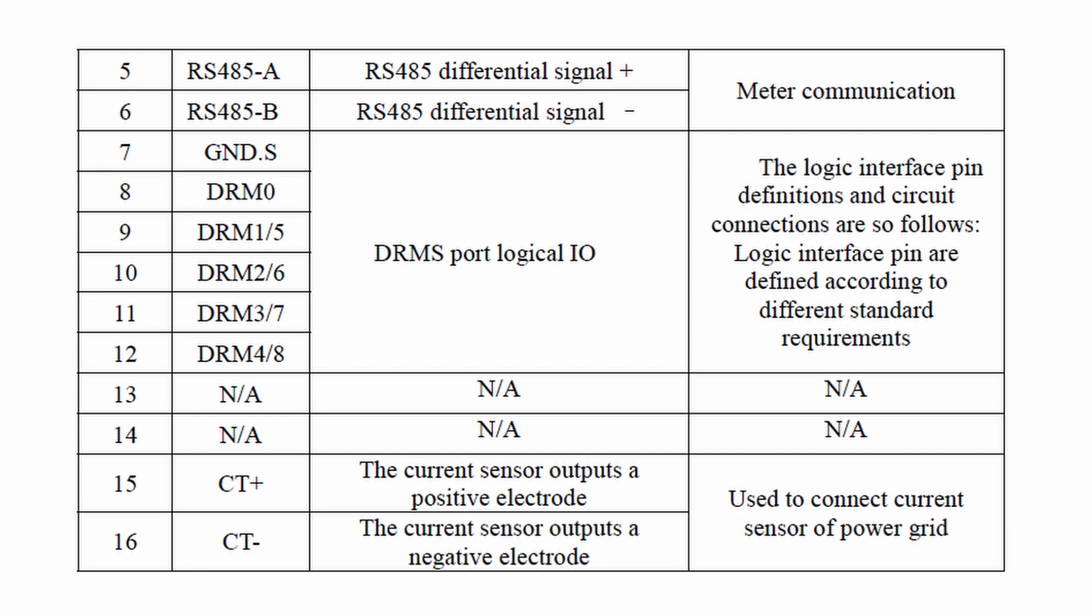The ratio on it is 2000 to 1. There's a dedicated meter and dedicated CT for that solution, which can be extended up to 1000 meters. The meter and CT need to be installed on the consumer unit or fuse board. The RS485 signal can then be extended down to the inverter.